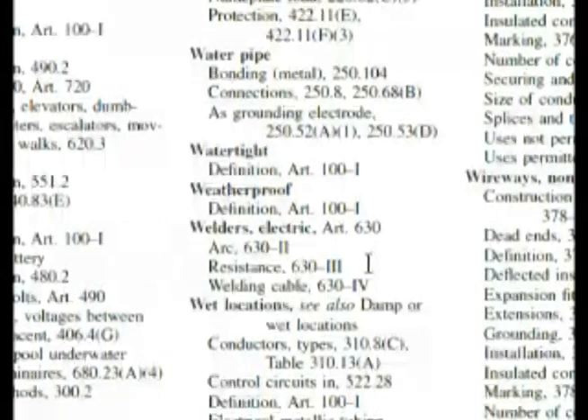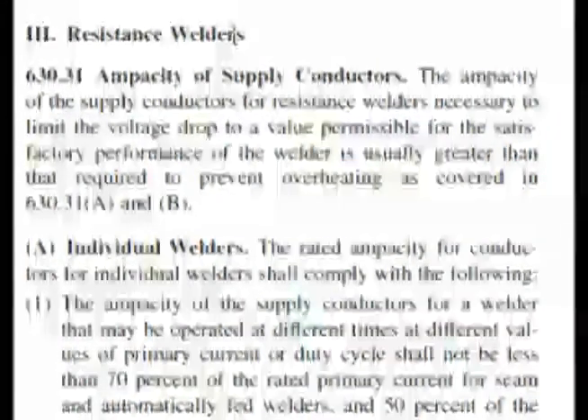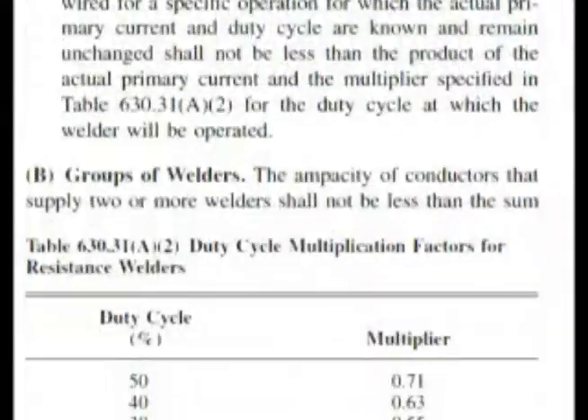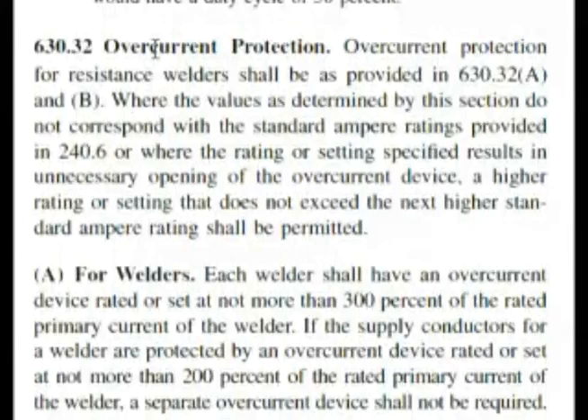Let's go and look at that section in the code book. Article 630-III on resistance welders — now we're looking for our overcurrent protection. Let's start reading the bold headlines on this and see what we can find. We scroll down this page and go to the top of the next page. We find that we're at overcurrent protection, and if we look down here, we have welders. As we read this, it's almost word for word of our question.